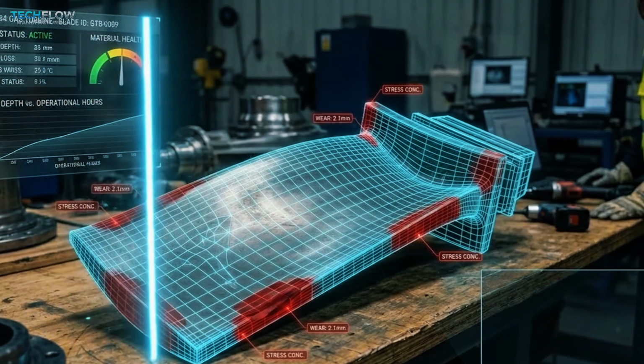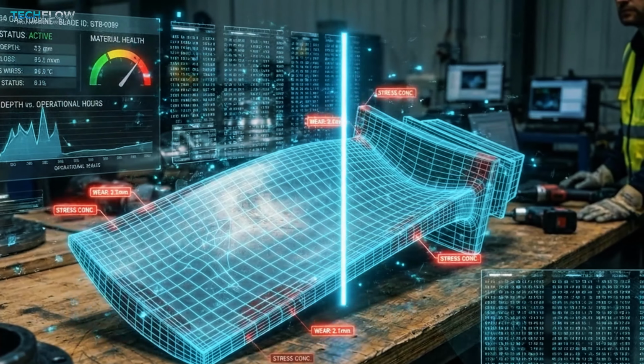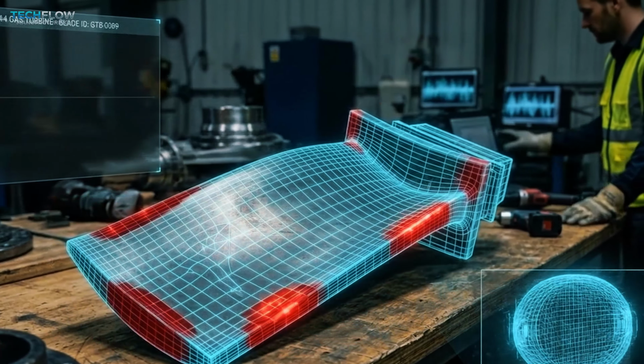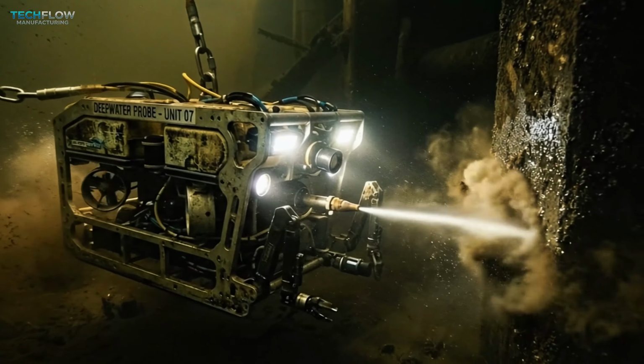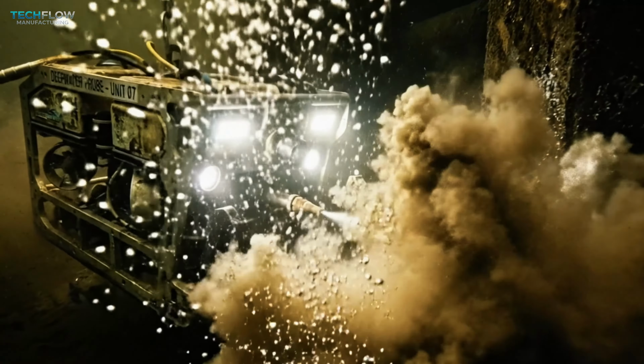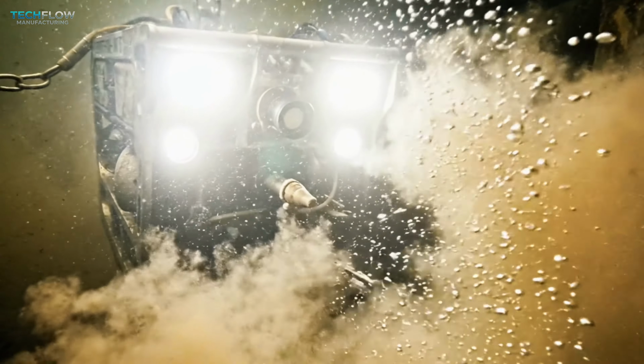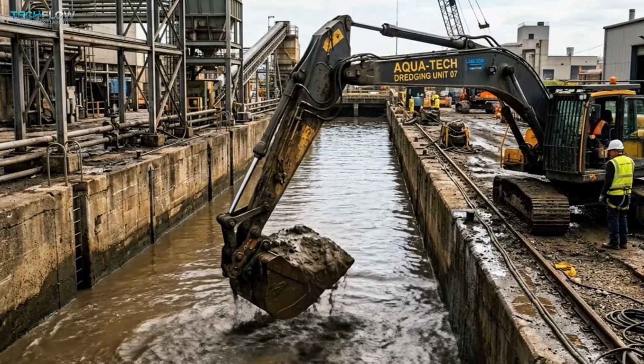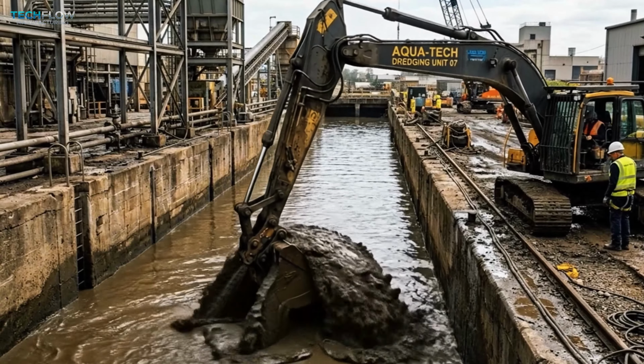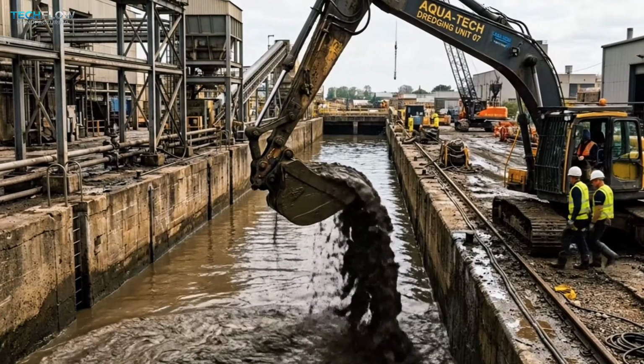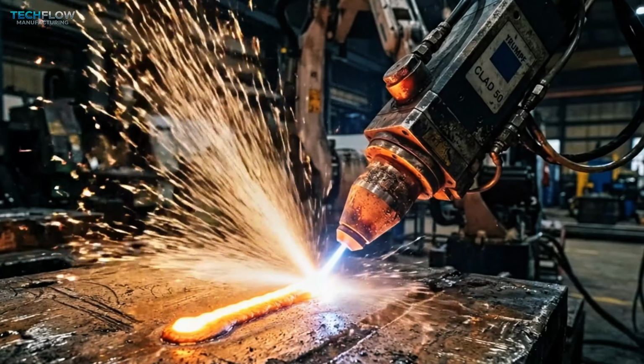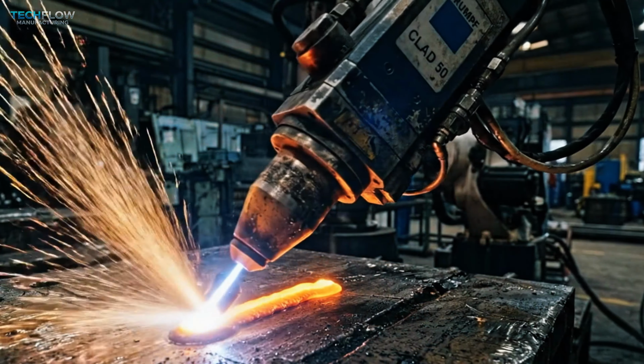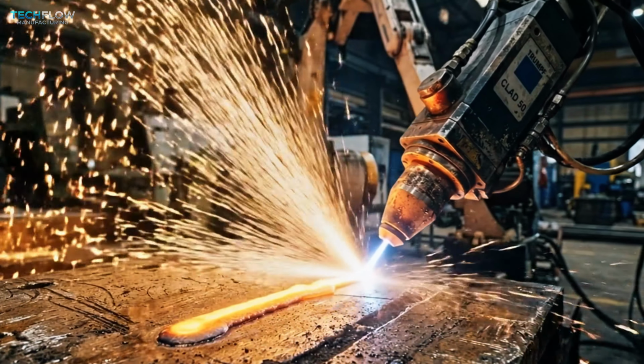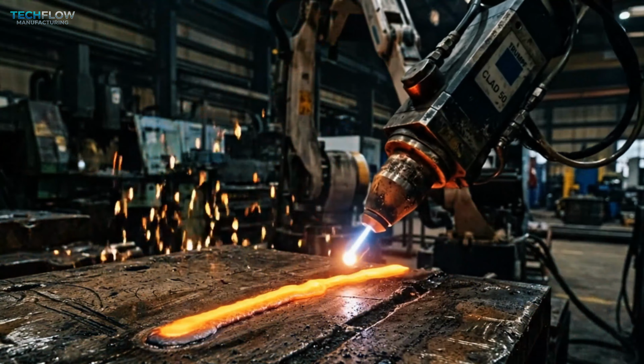Every square millimeter of the runner blades is mapped against its original digital twin to measure material loss. Underwater ROVs dive into the intake tunnels, clearing debris with high-pressure jets without stopping the flow. The silt and sediment of the Congo are constant threats, requiring automated dredging systems to keep the channels clear. We use laser cladding technology to repair worn components on site, adding layers of superalloy with micron precision.